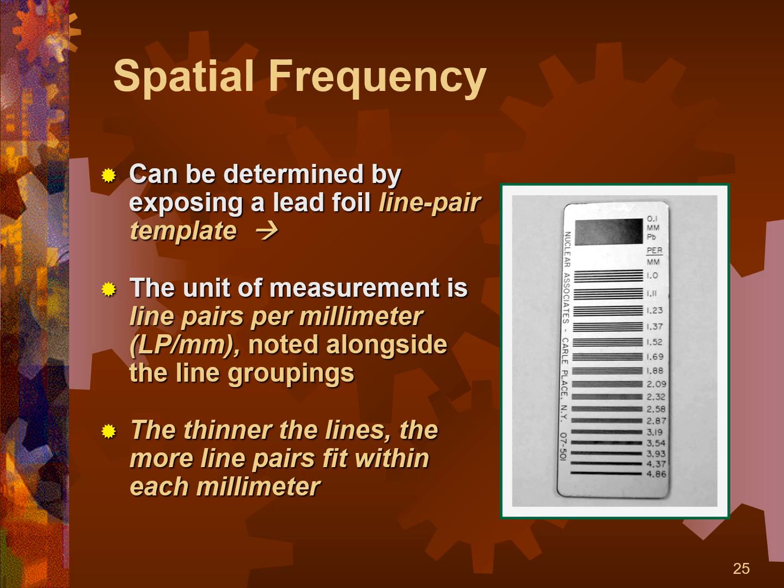Okay. So this is actually a radio opaque standard, and I have one of these. I think we do a lab on it. I'm not sure. There might be time for a lab on it. I hope there is, because it's a very fun lab. This is actually a slab of plexiglass plastic, and it's got lead strips embedded into it. And so you can actually X-ray it, and then you can figure out the resolution for your imaging system, which again is limited, as Carol points out, by the quality of your monitor.